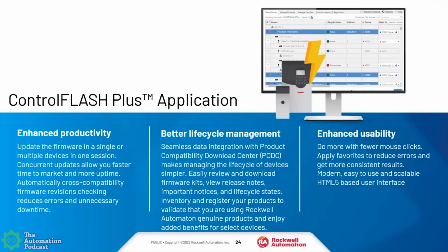There are going to be some limitations to this, such as the E300 and the PowerFlex. If you have those in a linear or DLR, those would get flashed sequentially. Certain comms cards, such as a DNB or ControlNet DeviceNet, have to be flashed before their children can be updated. So this would also be a limitation. But that being said, what is really nice is the tool can automatically figure out the order to flash those devices when they do fall in those exceptions.